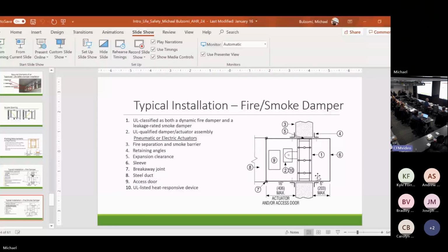Annular space, expansion gap, expansion clearance. Fire dampers, fire smoke dampers are made of metal. Metal gets hot, it expands. So if I had a 12 by 12 opening and I took a 12 by 12 damper and I pushed it in that opening, once it gets hot, fire gets close to it, the damper is going to expand. Those blades are not going to operate properly. They're going to start to warp and expand. So we have this expansion gap. It's a little bit different for every manufacturer, but generally it's somewhere in the magnitude of 1/8 of an inch per linear foot in width, plus 1/8 of an inch per linear foot in height. Minimum 1/4 inch, maximum plus 2 or 3 inches.